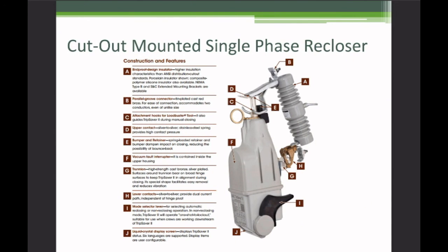Another thing that you might run into in terms of reclosers is S&C has a fairly new product out. It's called a Trip Saver 2, and they took an entire recloser, thanks to the wonders of computerization and miniaturization and how small those vacuum interrupting bottles actually are. They took an entire recloser, the computerized brain, the vacuum bottle itself, and they stuck it into a module that fits in a standardized fused cutout.